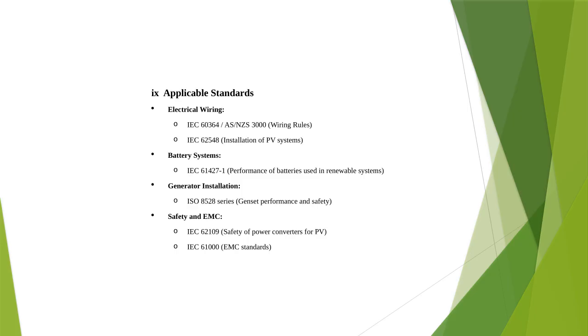Applicable standards. When it comes to wiring, our system is going to conform with the IEC 60364, AS/NZS 3000 wiring rules, and also IEC 62548 for installation of solar panel systems. For the battery systems, our system is going to conform with IEC 61427-1, on the performance of batteries used in renewable systems.